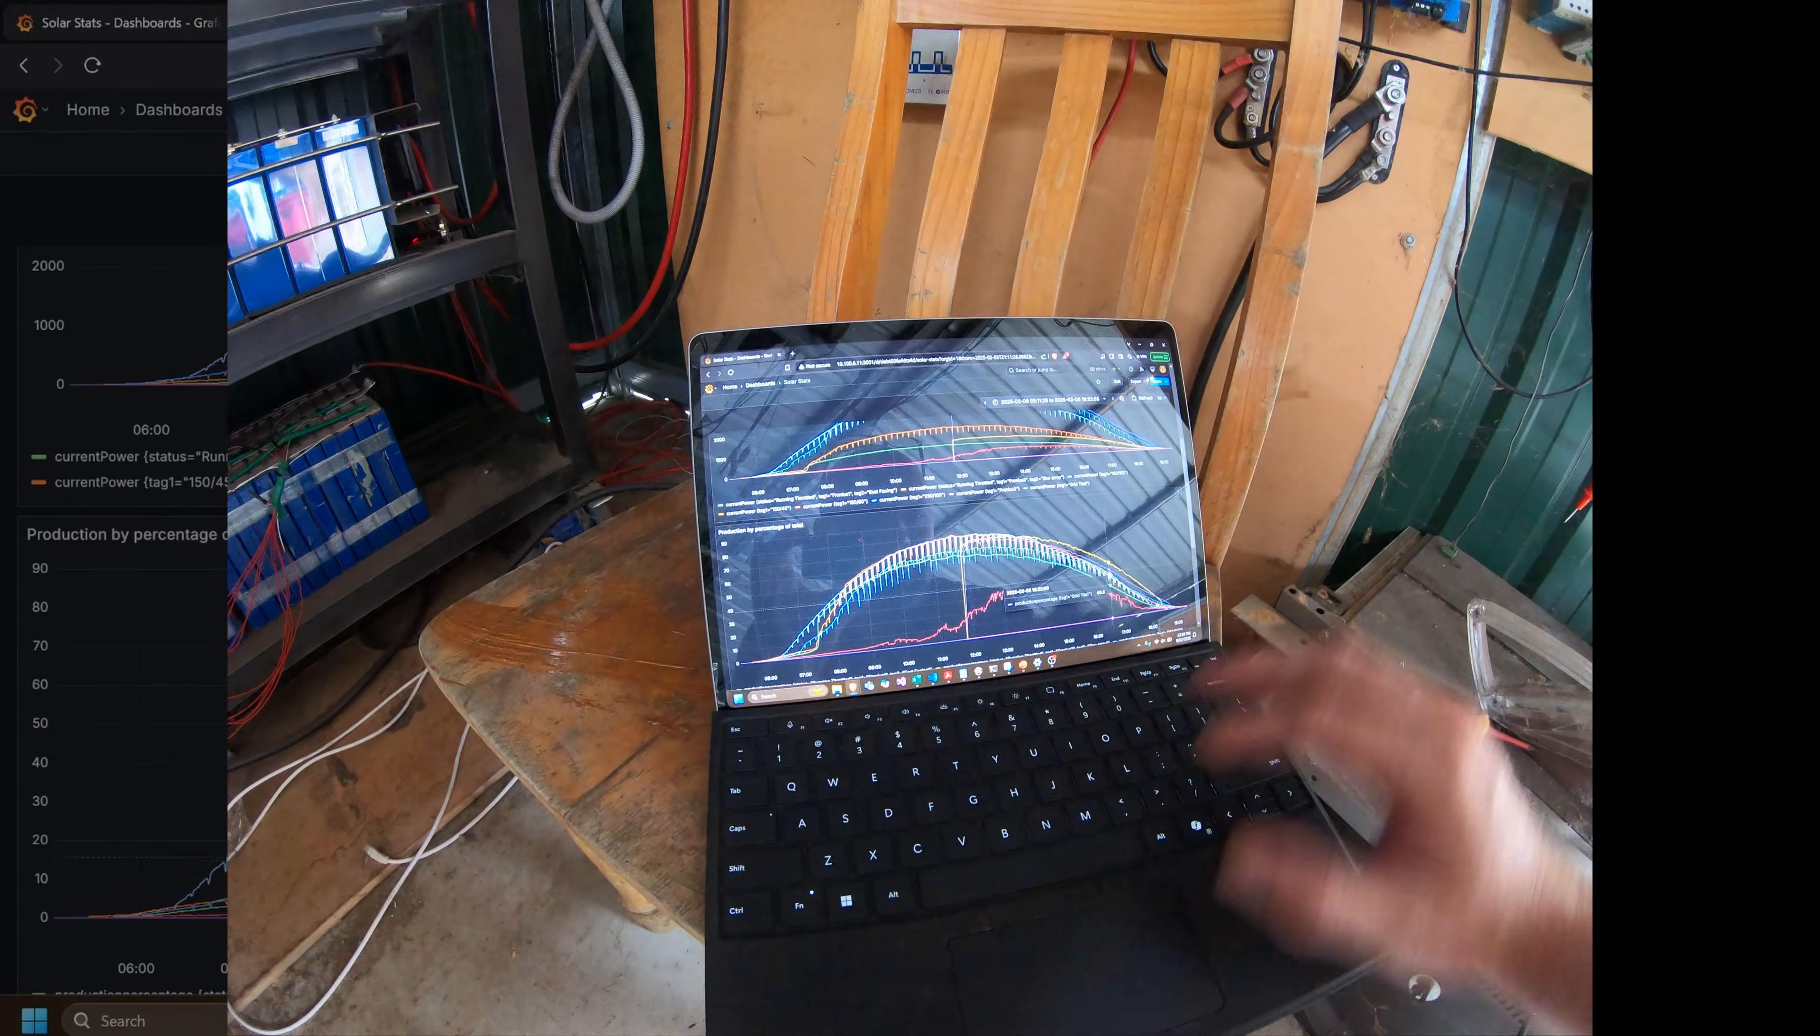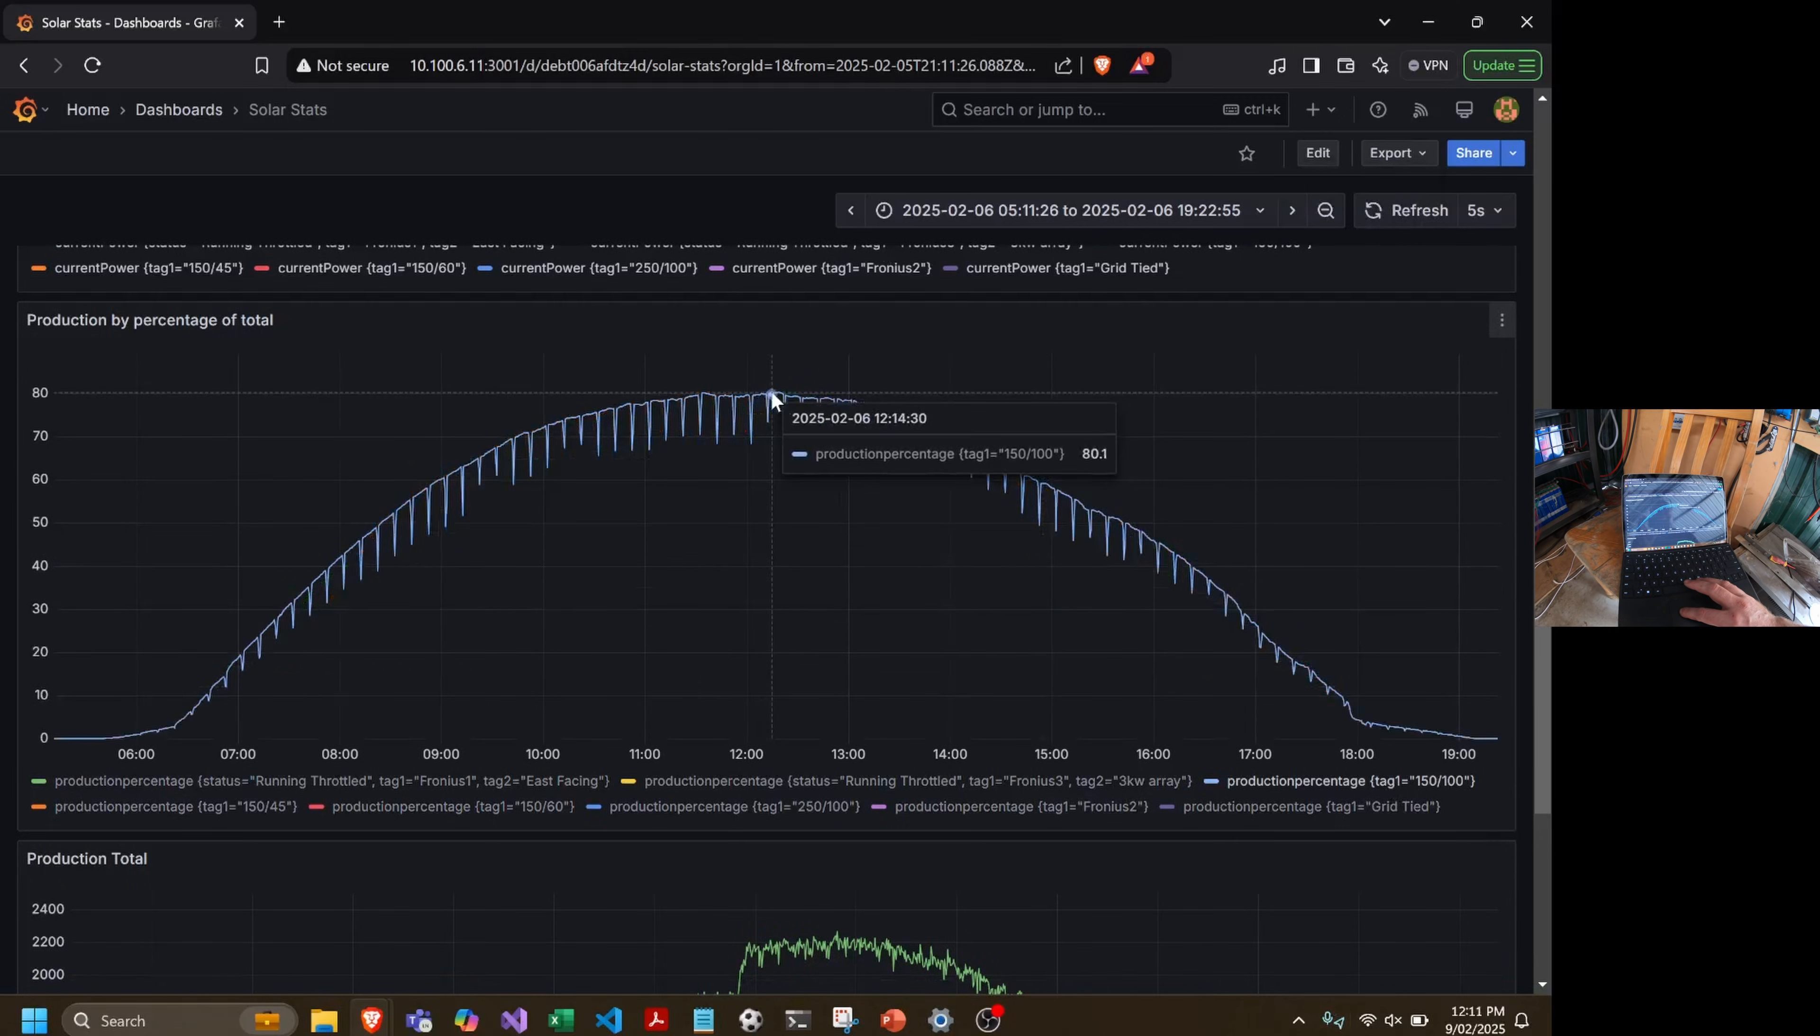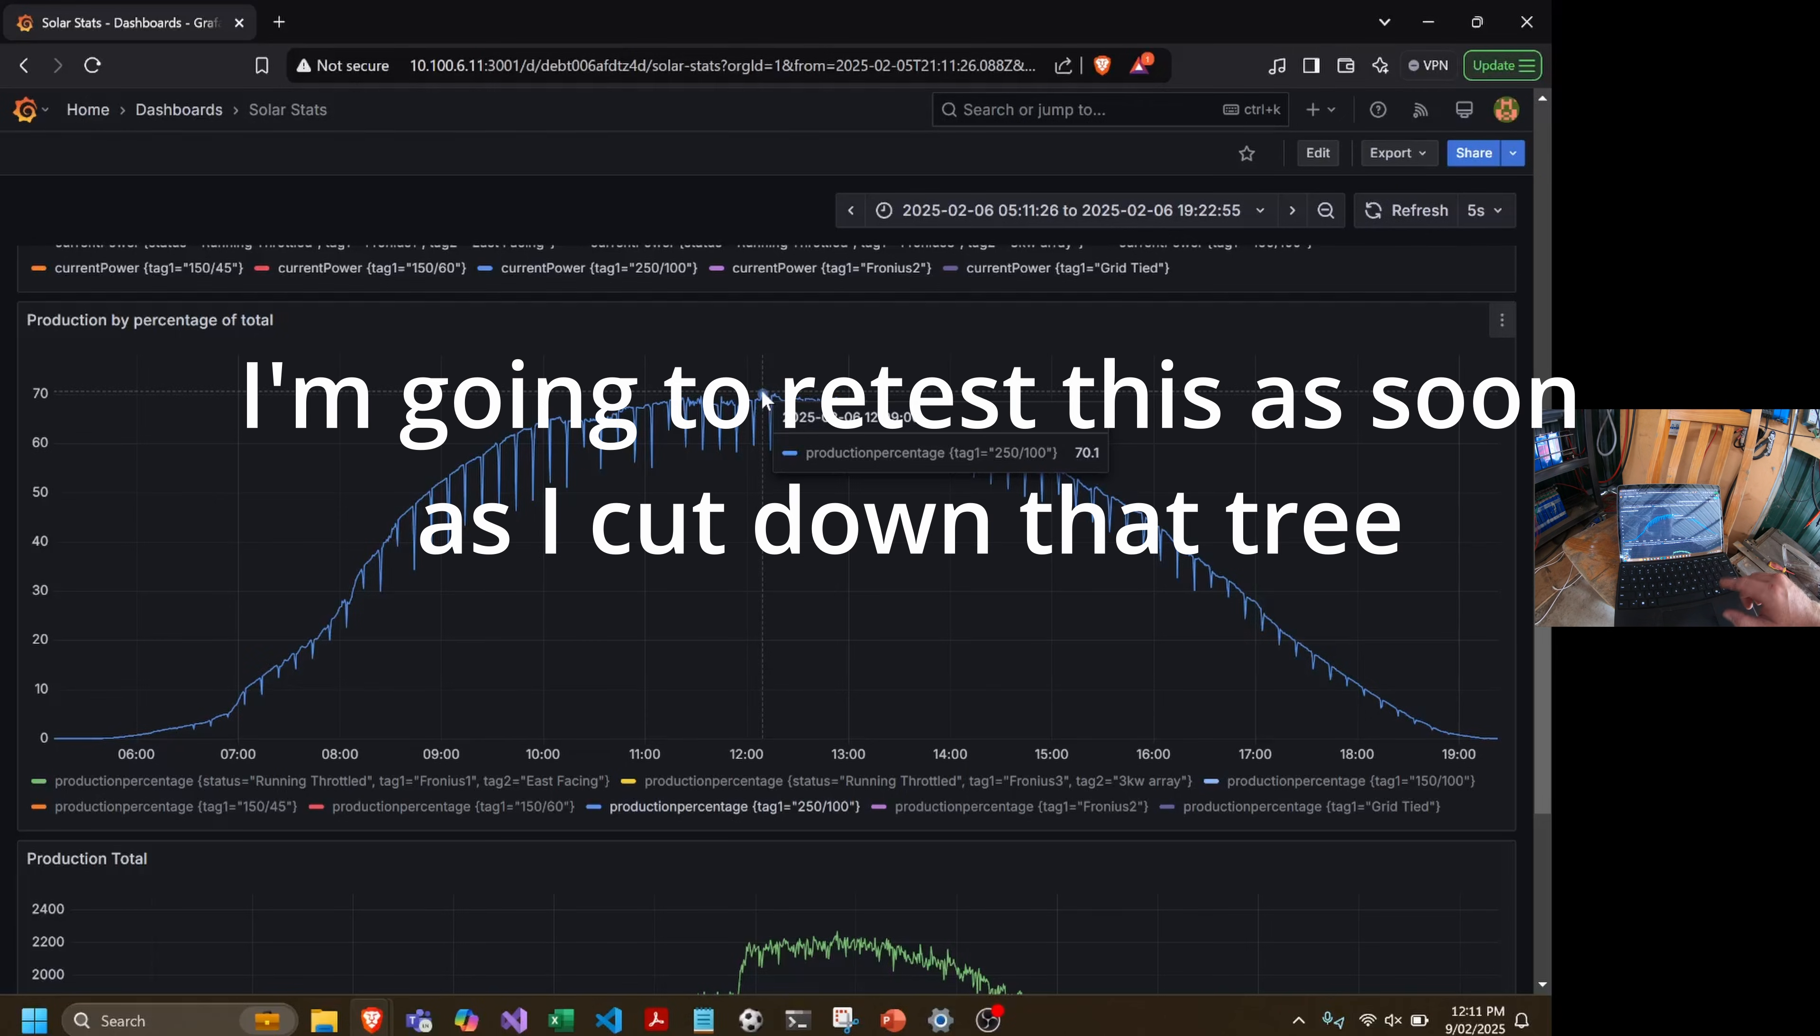So we want the 100 which was peaking at 80%, which is the array that's on the steeper angle. And then we've got this one, which is the other array made from the same panels, installed at the same time. It's only 70%. We're losing 10% of the performance of those new panels because they're simply on a shallower angle.